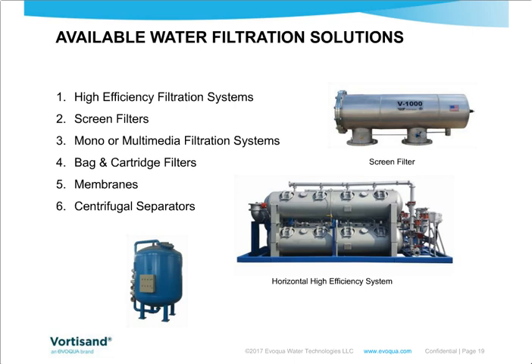Now, there's a number of different filtration methods and technologies or solutions out on the market today, from high-efficiency filtration systems to screen filters, such as large screens that can take down to maybe 100 microns. But these need to be cleaned at certain frequencies, requiring labor, mechanics having to shut down a process and clean those screens out, or maybe you could select an automatic screen filter. Multimedia filters are also very popular on the market today, but they're quite large in footprint. For the volume associated with your flow, this can cause a significant amount of footprint associated with those filtration systems. They also require high flow rates, potentially causing some channeling or other negative aspects of multimedia.